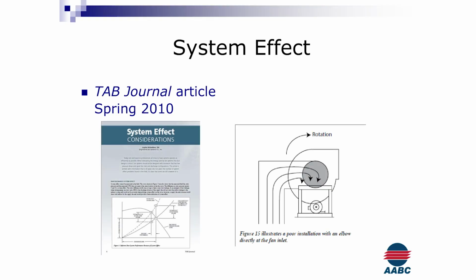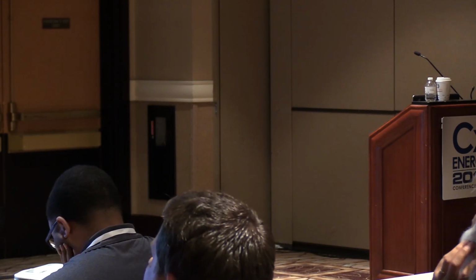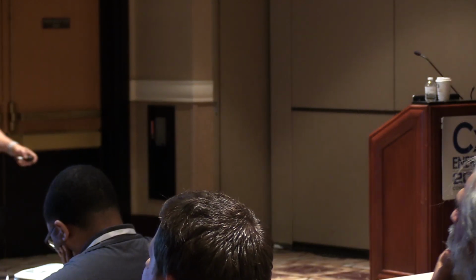And there's a great example showing you the rotation and what happens to the airflow. So the airflow is coming into the fan that has an elbow right on the inlet of it, and it's having to pull it almost a 360 before it even goes into the fan. I guarantee you that fan's going to work a lot harder to do what it's intended to do, and it's not going to ride on that beautiful AMCA fan curve, right?